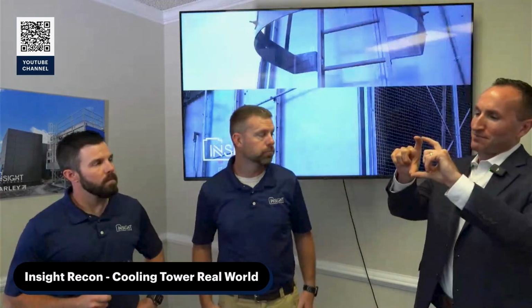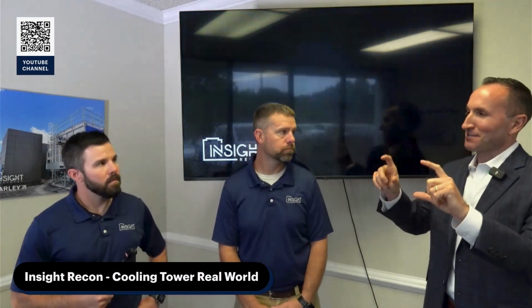Mm-hmm. And Justin, you pointed out, we were inside that cooling tower. You pointed out this neat little box that you said you could test by taking a hammer and hitting the side of the cooling tower. You sure can. Can you explain that? And what in the world is that little box that you were showing me that day? The vibration switch, one of the last parts in Steven's presentation, is going to be a switch that counts your inches per second that tower is going to see. And if it cycles over 0.6 inches, or 0.7 is our shutdown, 0.6 is an alarm and 0.7 shutdown, it's going to turn the fan motor off so that tower doesn't eat itself.